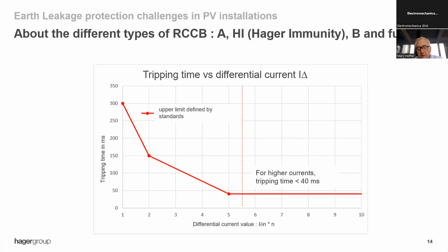You see that above 5, so 5 times 30 is 150 milliamps, even the high immunity RCCB is tripping very fast, same speed as the classical one. So we are then also at 40 milliseconds. The type A is not sensitive to the level of differential current, or very, very little. But the classical high immunity is sensitive to this. Therefore, it's important to know what is a real leakage current, what is the value, to know what could be the appropriate solution. Because if this current is very high, even high immunity products won't work, because they will trip too, because the leakage is so high that they will trip quickly. That means quickly, before this transition is finished.